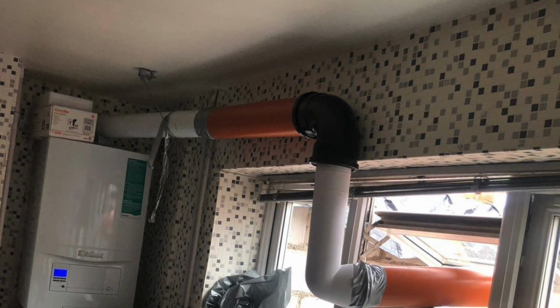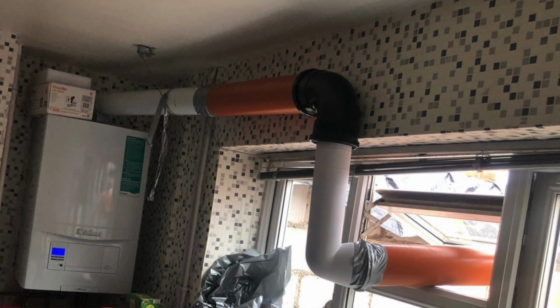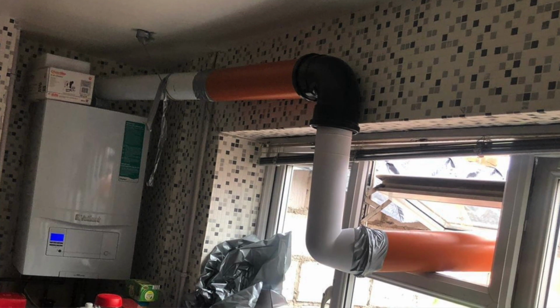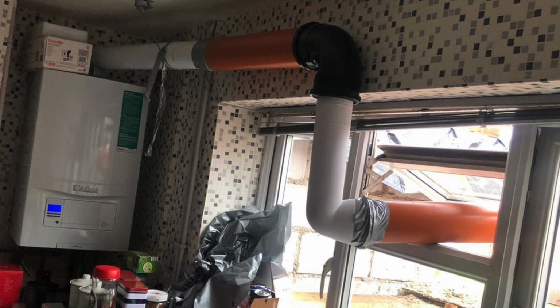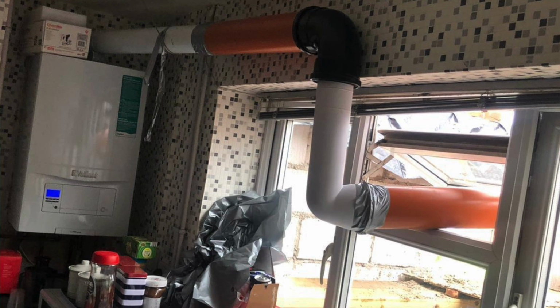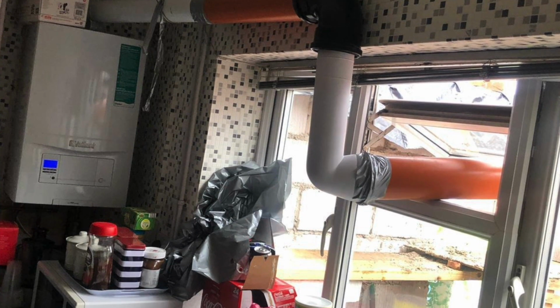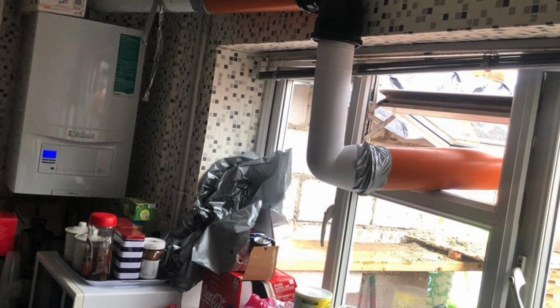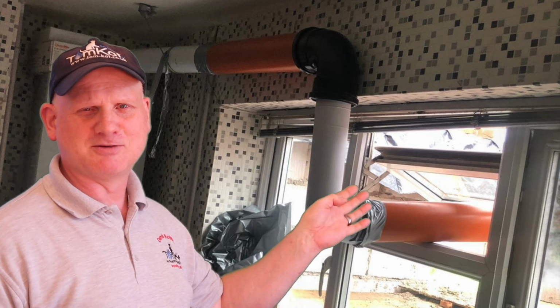This one represents you going to price up to move a boiler for a self-build extension. So there's no builder involved in this. The actual homeowner is sorting it all out themselves and getting individual trades in to do the jobs. And you rock up to give them a price to move the boiler. And the customer is proud of the way they've diverted the products of combustion while the brickies are bricking up the extension. I love this picture. I think it's amazing. I love the way they've used the toilet pan connector to bring it down with the waste pipe. I think it's amazing.